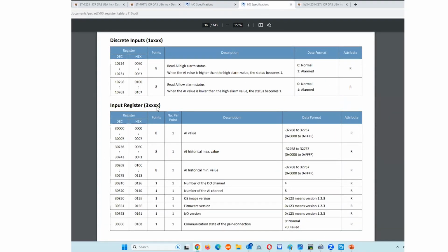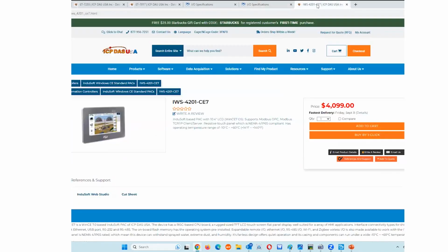Some of the Modbus register table as shown here, simply just monitor the 30,000 registers or 3x registers for the analog input values, along with the digital inputs, digital outputs from other modules or other PLC sources within your application. When you tie this all together, our IWS touchscreen monitor can be used with this. Indusoft Web Studio is installed on this, and you must purchase a development license. But once you create your application, you could create a visual representation of your control panel, your application, and just control and create logic with it to coordinate with the motion control from the mechatronics application that you develop.